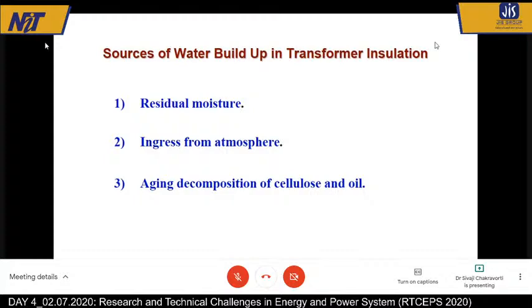0.5% by weight. Generally, it is 0.3% by weight. Then ingress from atmosphere means that if the sealing of the transformer is not good, because the transformer has a top tank, it has an oil drain valve, etc., then moisture will come in. It is very low because of care.